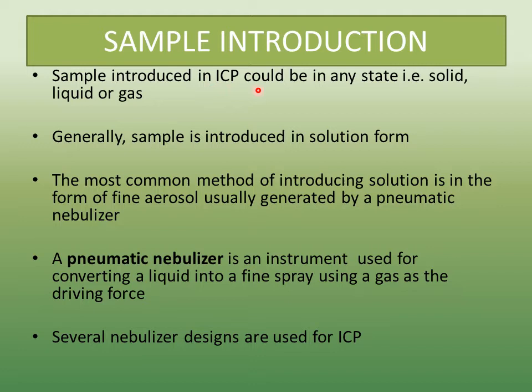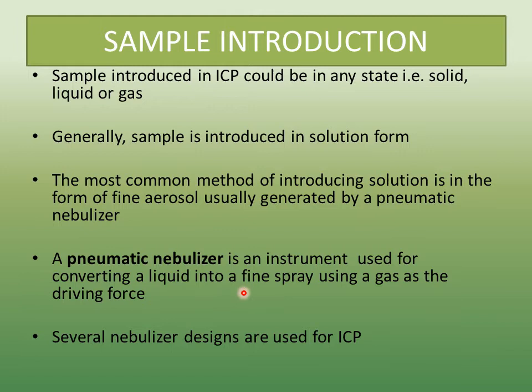Samples introduced into inductively coupled plasma can be in any state — solid, liquid, or gas. However, generally the sample is introduced in the form of a solution, and the most common method is introducing it as a fine aerosol, meaning the sample solution is introduced as fine droplets mixed in air. These are usually generated by the use of a pneumatic nebulizer. A pneumatic nebulizer is an instrument used for converting a liquid into a fine spray using a gas as the driving force.